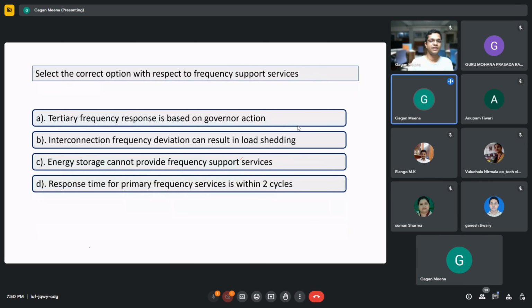So E is correct. Next is select the correct option with respect to frequency support services. Tertiary frequency response is based on governor action. Interconnection frequency deviation can result in load shedding. Energy storage cannot provide frequency support services. And response time for primary services is within 2 cycles. B is the answer. D is not correct, I think. B should be correct. Primary frequency services will respond within seconds, and one cycle is 20 milliseconds. Millisecond range, only inertial support can provide.